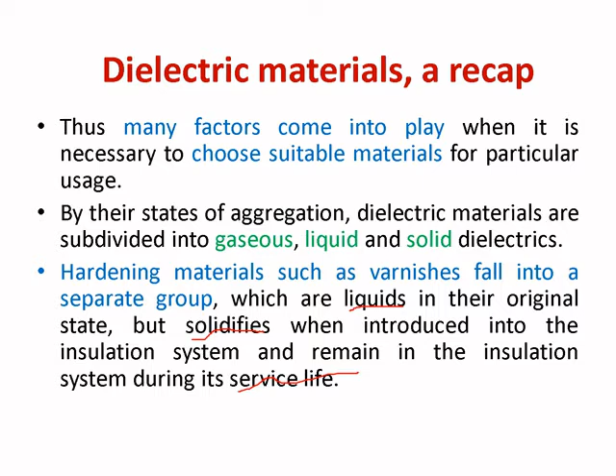Dielectric materials are divided into three different categories: solid, liquid and gaseous. For example, air and SF6 gas are examples of gaseous dielectric insulating material. Liquid dielectric insulating material is again divided into two parts: natural and synthetic. Transformer oil comes under the natural liquid insulating materials, and ascarel is a synthetic liquid insulating material. Solid insulating material is divided into organic polymer, fibrous material, ceramics and a combination type of insulating materials, that is, oil impregnated paper. Ceramics are like glass, porcelain, and fibrous materials are like paper and asbestos.